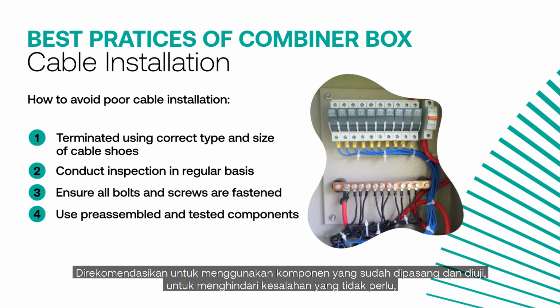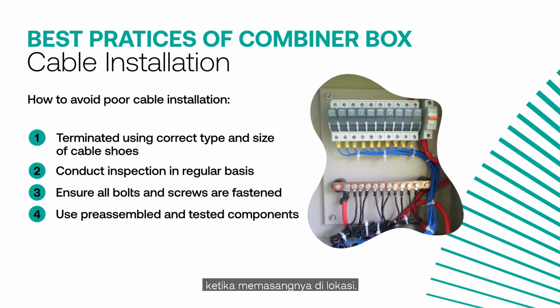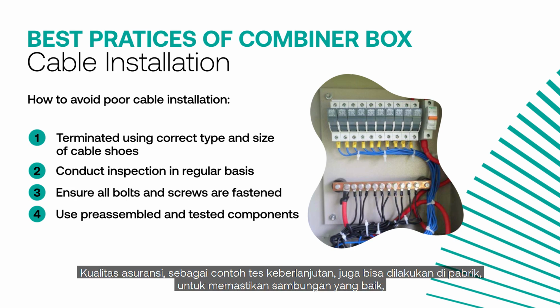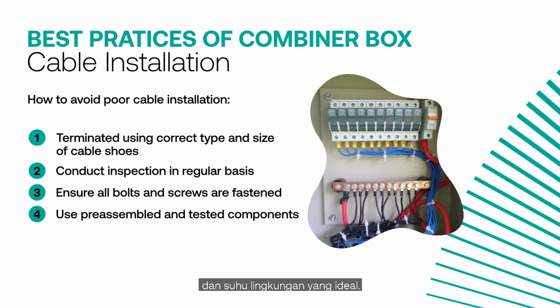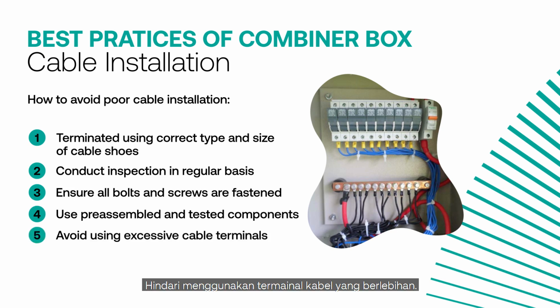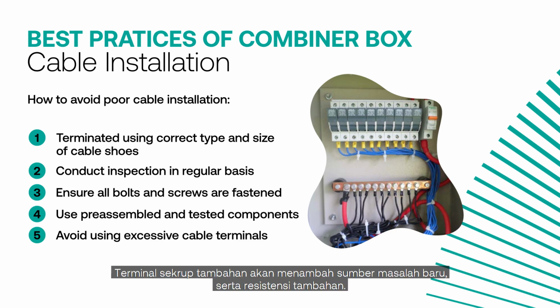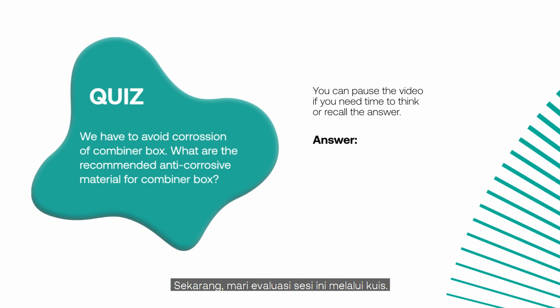It is recommended to use pre-assembled and tested components to avoid unnecessary mistakes when performing assembly on site. Quality assurance, for example a continuity test, may also be conducted in the factory to ensure a proper connection and ideal ambient temperature. Avoid using excessive cable terminals. An additional screw terminal will add a new source of problems as well as additional resistance. Now let us evaluate this session by doing a quiz.